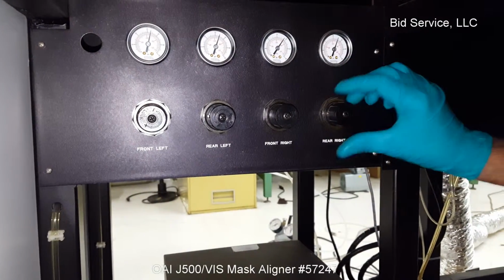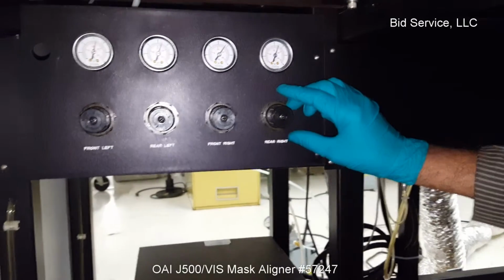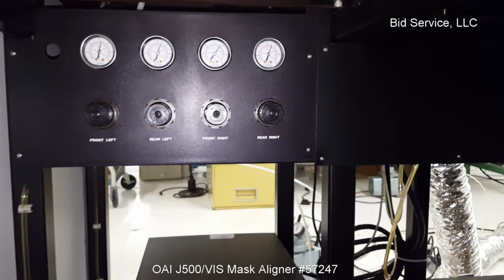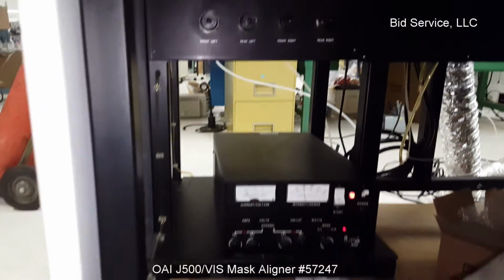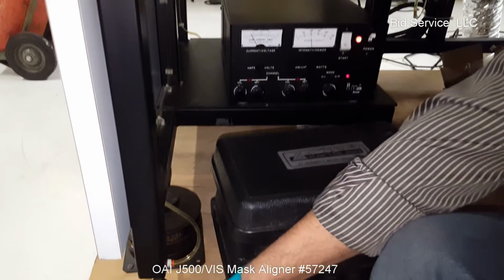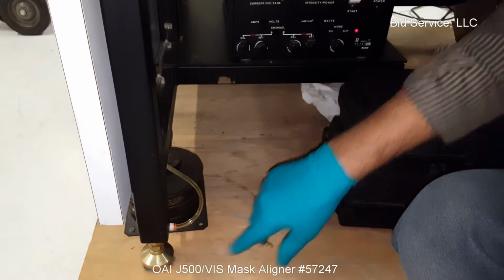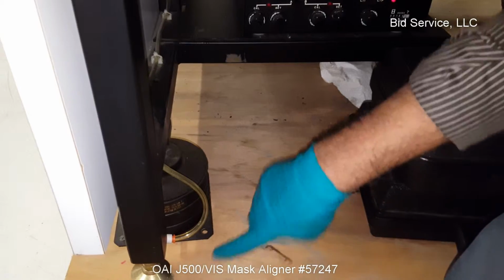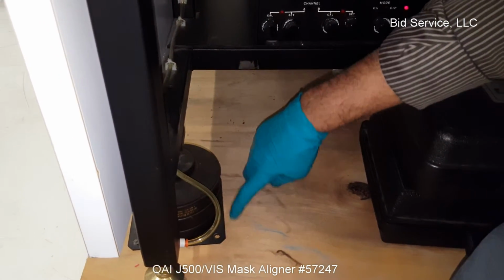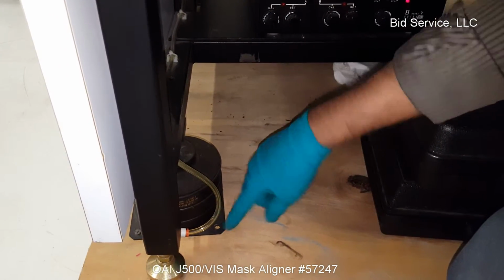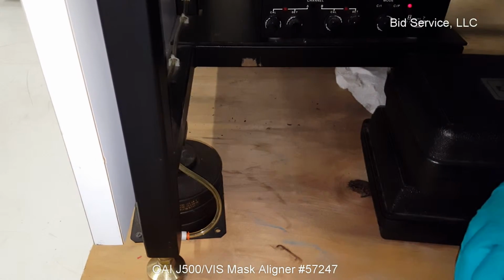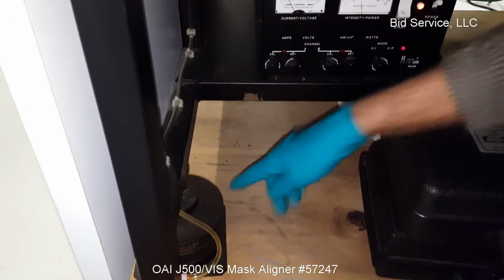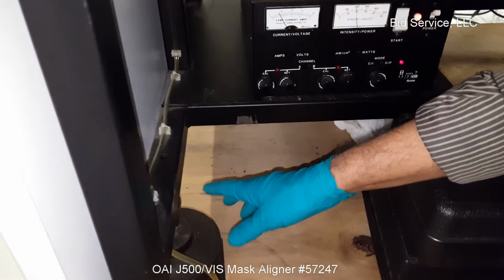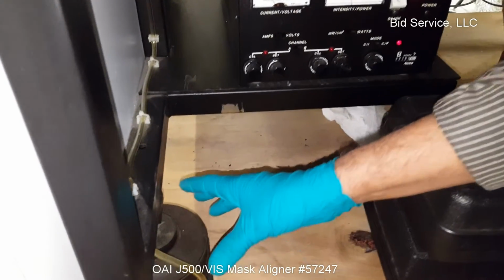The pressure should be adjusted in such a way that the stable feet, which are here, should not be touching the floor. So at the final site, if necessary, an aluminum plate can be used to lift up the bellow a little bit. When the unit is shipped, these bellows will be disconnected.